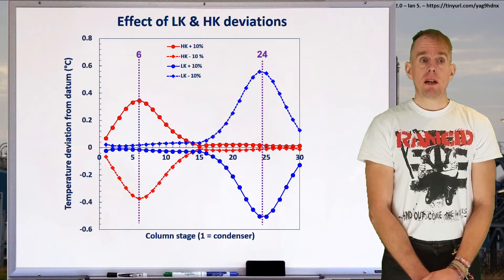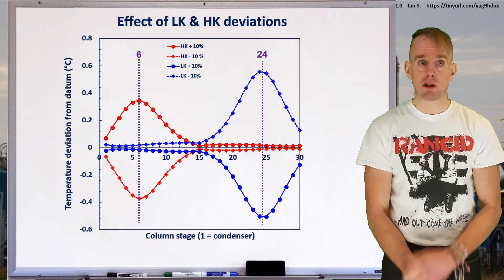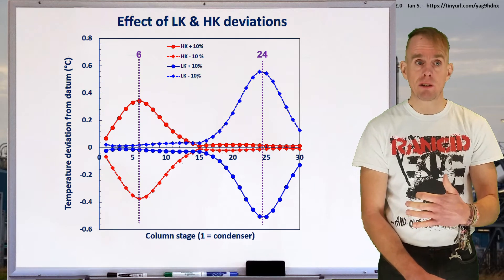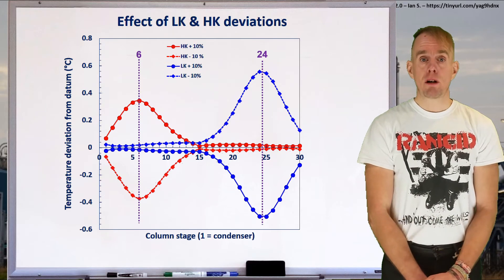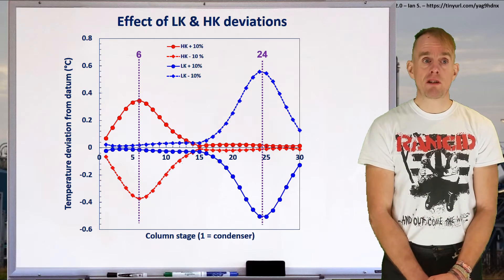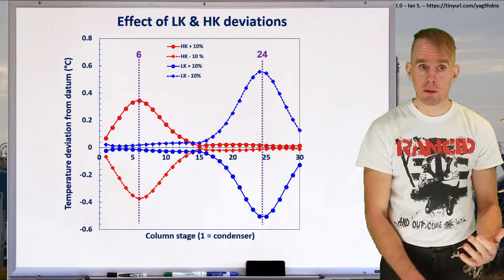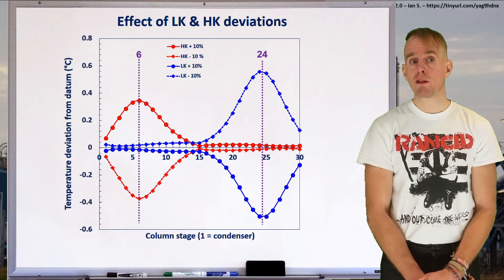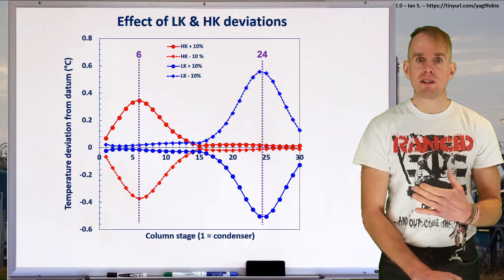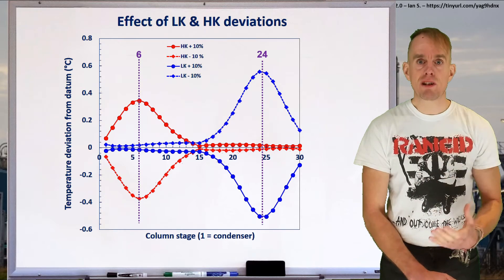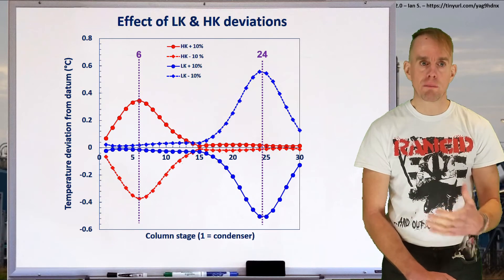We also see that at various points in both the rectifying section and the stripping section there's a bigger temperature deviation compared to anywhere else. Looking at these data, it might be appropriate to say, let's start to think about measuring temperature deviations at tray 6 for the top of the column and at tray 24 for the bottom of the column, because this is where our largest temperature swings are — which means it's going to be easier to measure those temperature changes and get a fast result with which we can control composition specifications.